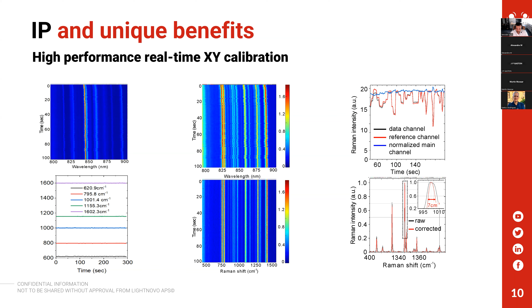So here we see an overview of miniRaman models. There is miniRaman standard with one laser, 785 nanometers, with power 5 to 50 milliwatts. miniRaman power, also 785 nanometers, but with increased power specifications up to 90 milliwatts. miniRaman SERS, it's again a 785 laser, but with power well tunable in the low power range, suitable for surface enhanced Raman. miniRaman standard dual with an additional 660 or 675 nanometer laser, and miniRaman power dual with increased power in the second channel, 660 or 675 nanometers.